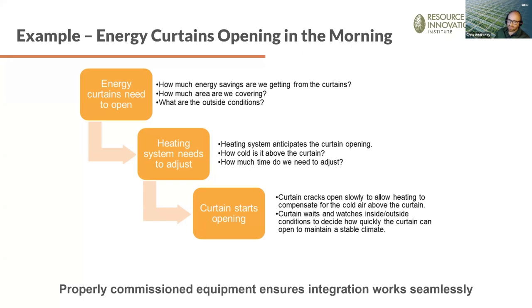After that curtain cracks open slowly, it gives a chance for the climate to adjust, and the curtain is going to make another move. So it's going to wait and watch the inside and outside conditions to decide how quickly the curtain can open to maintain a stable climate. At the end of the day, when we're opening that curtain, we want to make sure that we're not opening the curtain too quickly, which is going to cause a dip in the temperature. Or say we offset the heat and the curtain doesn't open properly, then we're going to get a rise in temperature as well. So properly commissioned equipment ensures that integration works seamlessly and ensures a stable climate. Next slide.